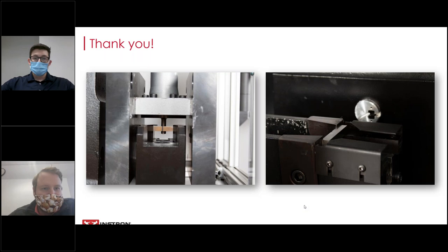Yeah. So in a perfect world, when you break a specimen, you only want to know how much energy it took to break that specimen. But when your hammer is swinging down to achieve the velocity that you're looking for, you're going to have wind loss just from the hammer flowing through the air, and also friction loss. Also, you lose some friction energy when you break the specimen, as the specimen is being forced out of the supports. There's a little bit of energy loss in that friction. So it's important to calibrate your machine.